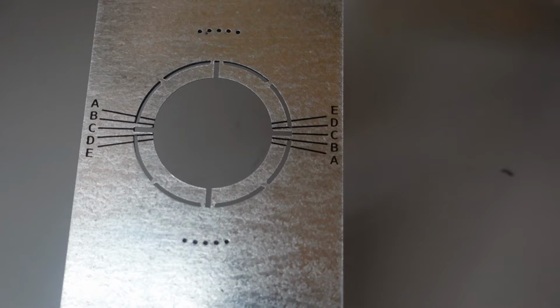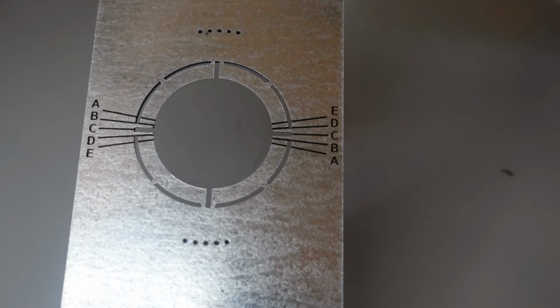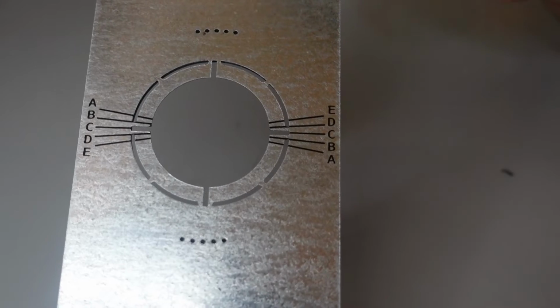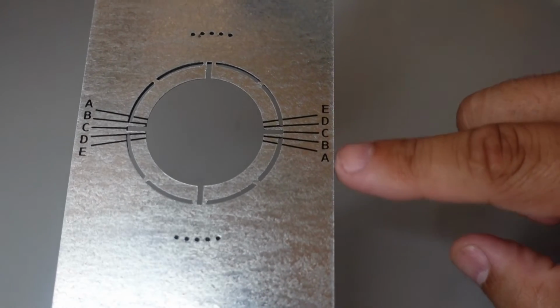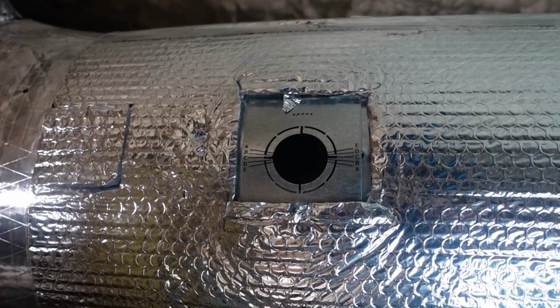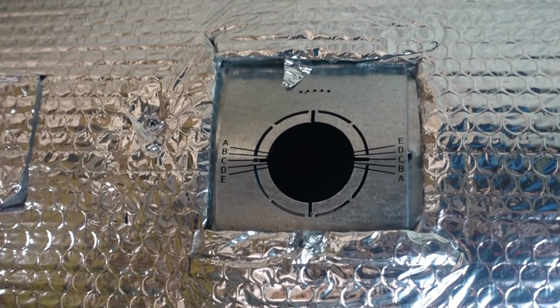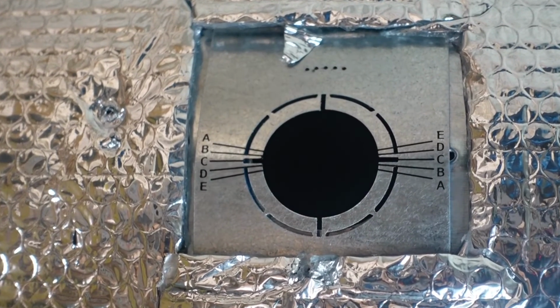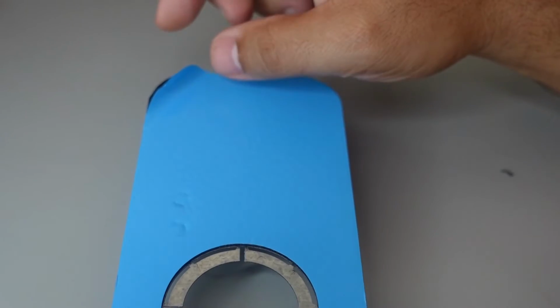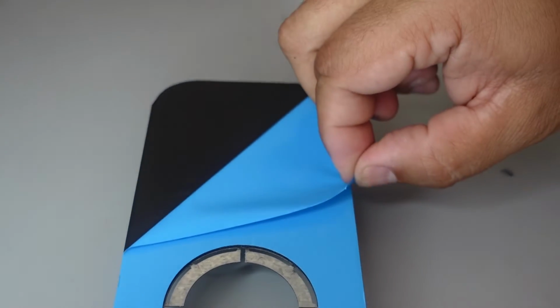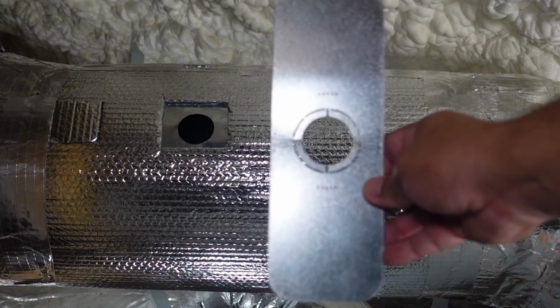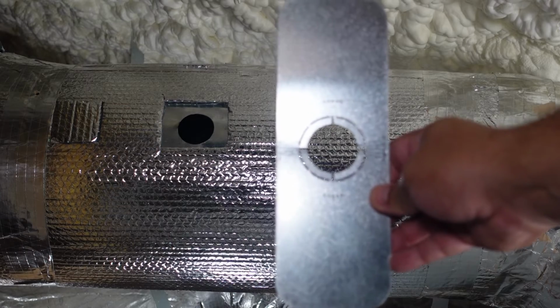If your monitor came with a metal alignment plate, now's the time to get it out. This is mainly designed for ductboard installs and is an optional add-on for metal ductwork. It's recommended for all installs since it provides position markings that are useful during the airflow validation process, as well as extra sealing. Peel off the backing and position the alignment plate perpendicular to the airflow on the ductwork.